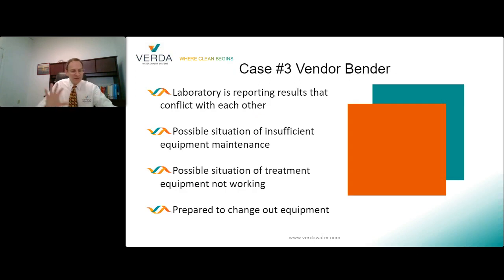All right, I want to talk about another case. It's a fun case study because we're going to talk about a facility that had no problems. So as part of a monthly water testing to validate the SPS water quality, water hardness and conductivity was tested on the critical water. That is the water used for the final rinse at the three-basin sinks and the washer disinfectors. Now the AAMI TIR34 guideline recommends that the final rinse water conductivity be very low, right?